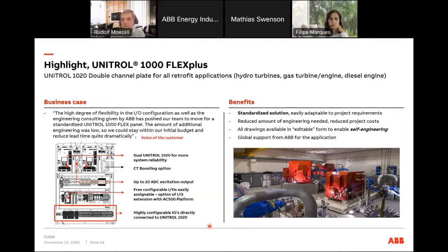On the right side, you see this was a project they did - a pump storage project, if I'm right, where they even used changes of the parameters. With this plate, you have all the flexibility you need to make retrofit projects happen. Please remember, even when you replace a UNITROL-7 or -15, you might already have a plate installed there. Typically, this plate size will fit there as well. Also, you would need anyway to build up such a system, and it would be, in my opinion, much easier to use than the flex plate.